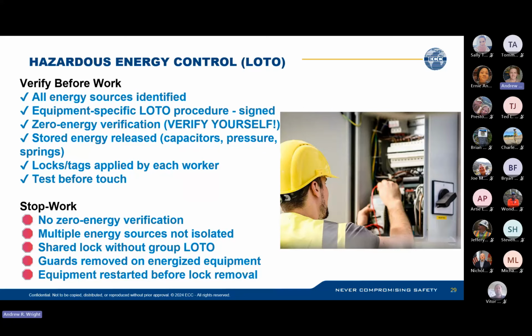Real quick side note, even if you call out the boss contractor or utility owner and they say, yeah, everything's good, the gas line is off or whatever is off, verify yourself, because I had this happen to me. They told us, oh yeah, the gas is off, we turned it off, and they opened up the bleed valve to let the system drain out, and it just kept going and going and going. What had happened is they turned off the wrong gas system, so my gas lines were still energized, and we were going to do work on it. So I had to get them back out there and basically say, no, you guys messed up. You didn't cut off the right system. So make sure you're actually double checking it yourself, especially when there's a lot to lose on the line.